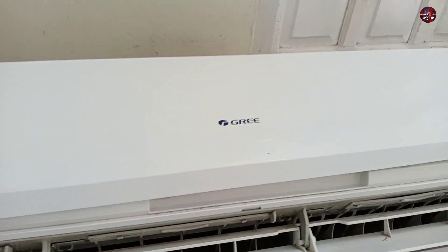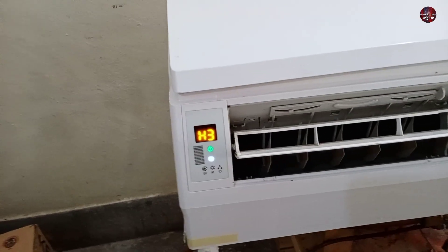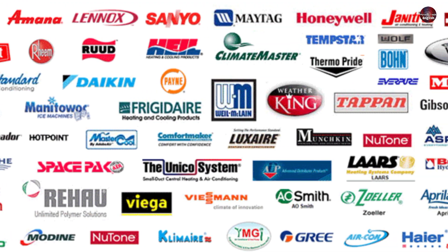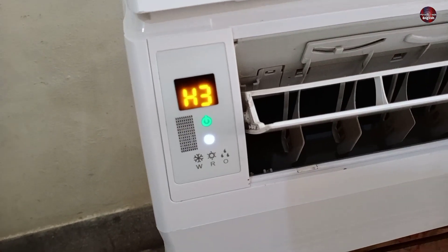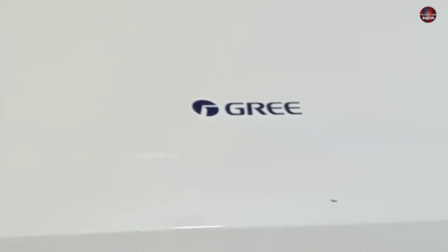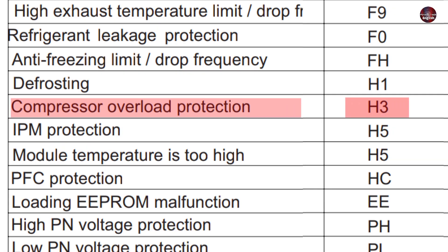This is a GREE inverter mini split air conditioner, which is showing an H3 error code on its display. H3 is also shown on many other brands of mini split air conditioners, and the meaning of the H3 error could be the same for other brands. The H3 indicates a problem in your outdoor unit, meaning the overload protection for the compressor is faulty or has been turned off.